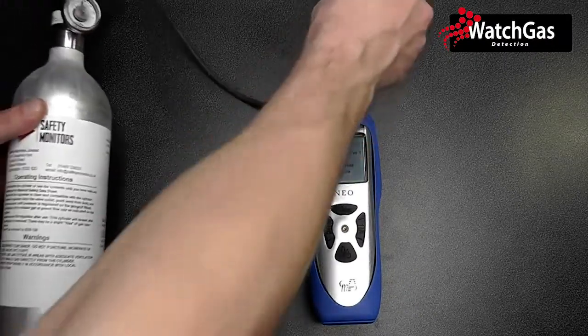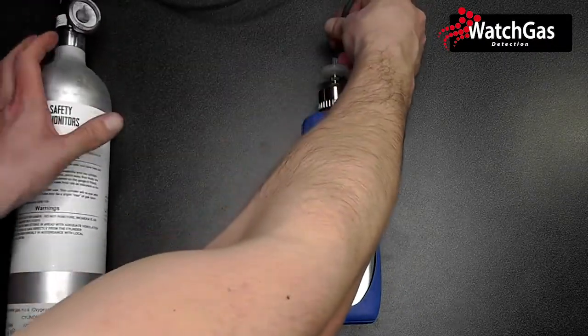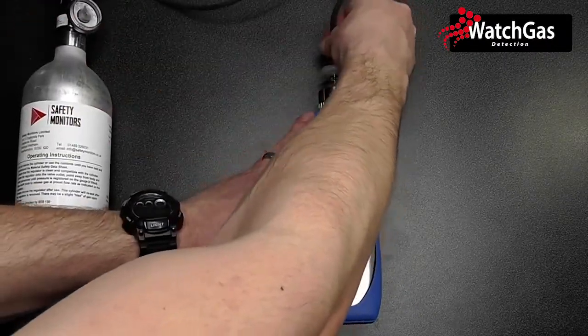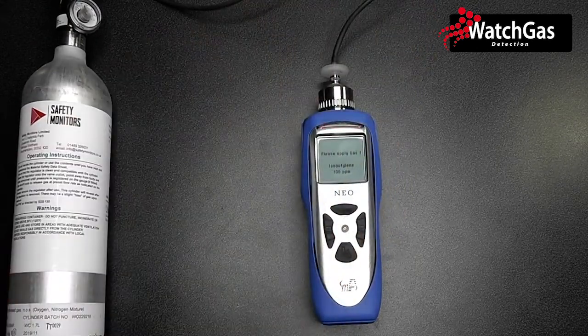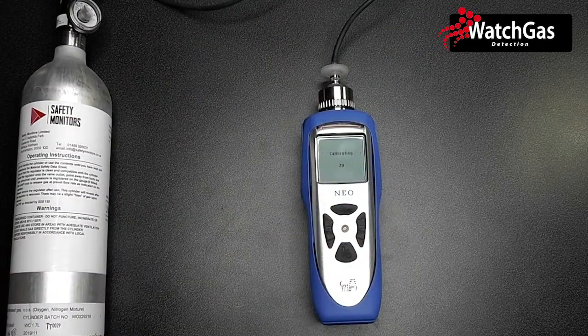I have a can of isobutylene here, so I can apply this to the end of the device. Because this is a pumped instrument, I can use an on-demand regulator. And we can see the instrument is now calibrating. Calibration takes around 30 seconds for a full span calibration. So we'll just watch that tick down.